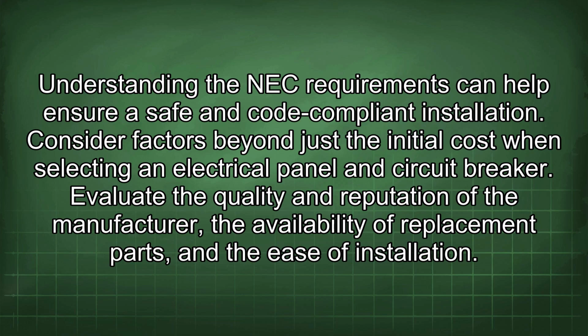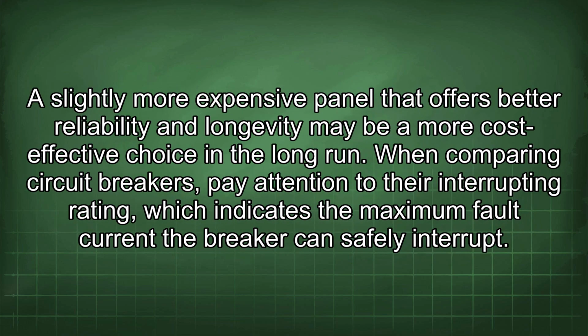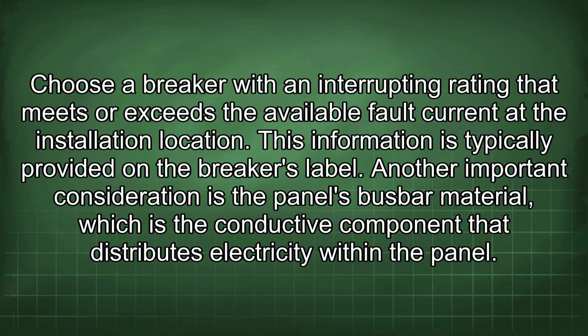Consider factors beyond just the initial cost when selecting an electrical panel and circuit breaker. Evaluate the quality and reputation of the manufacturer, the availability of replacement parts, and the ease of installation. A slightly more expensive panel that offers better reliability and longevity may be a more cost-effective choice in the long run. When comparing circuit breakers, pay attention to their interrupting rating, which indicates the maximum fault current the breaker can safely interrupt. Choose a breaker with an interrupting rating that meets or exceeds the available fault current at the installation location. This information is typically provided on the breaker's label.